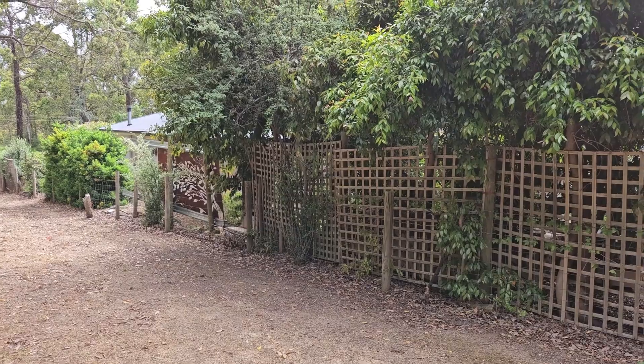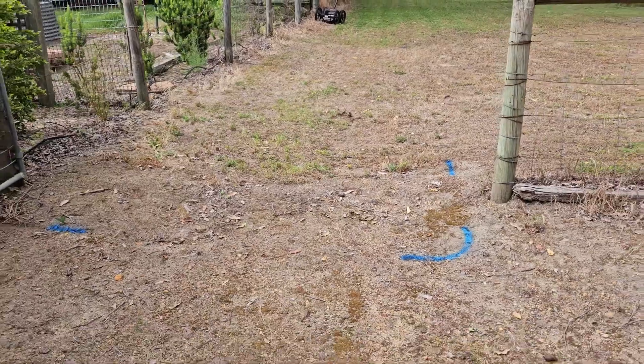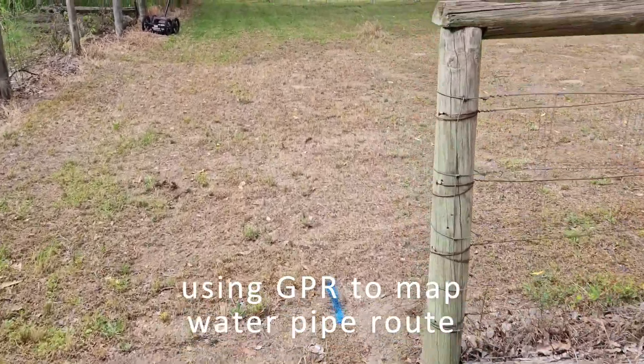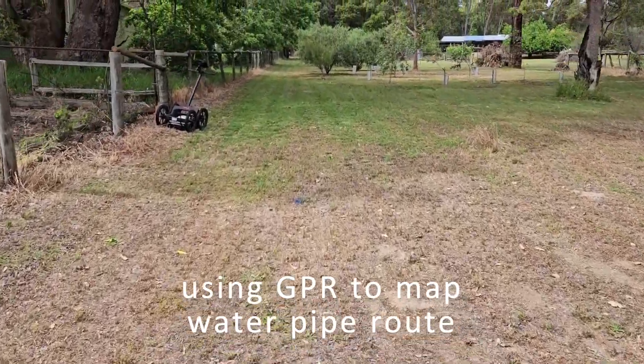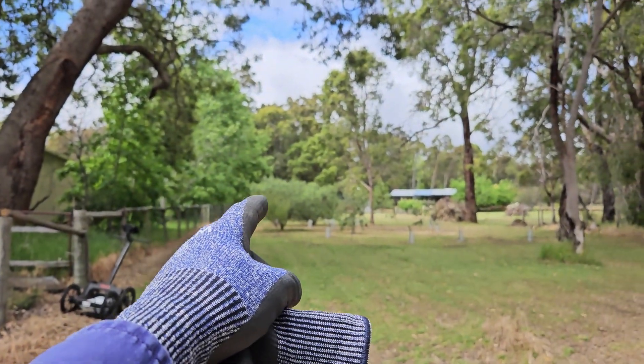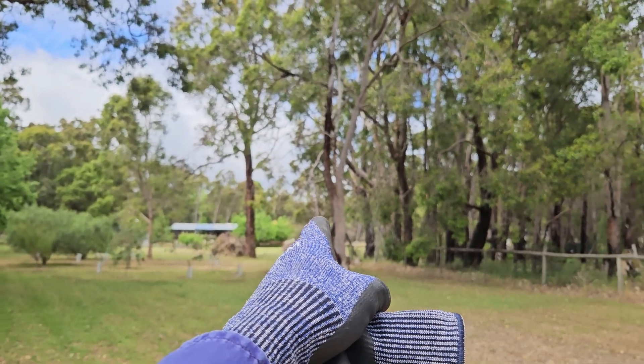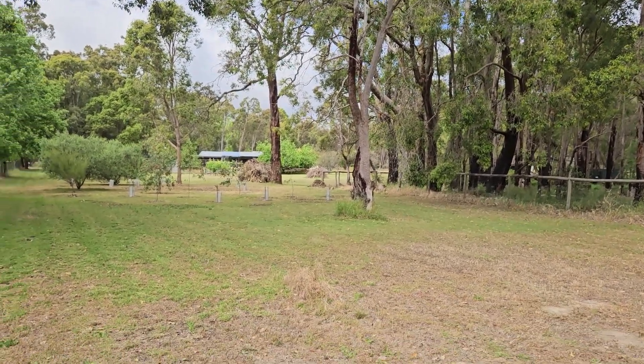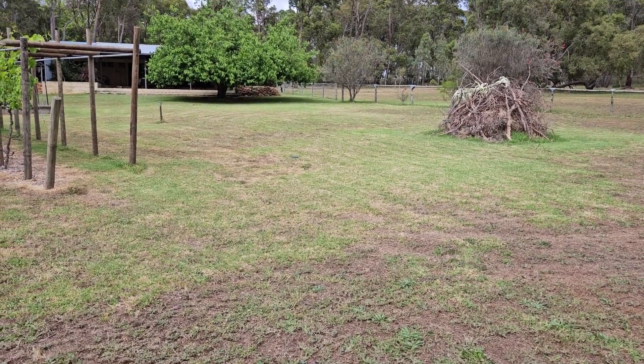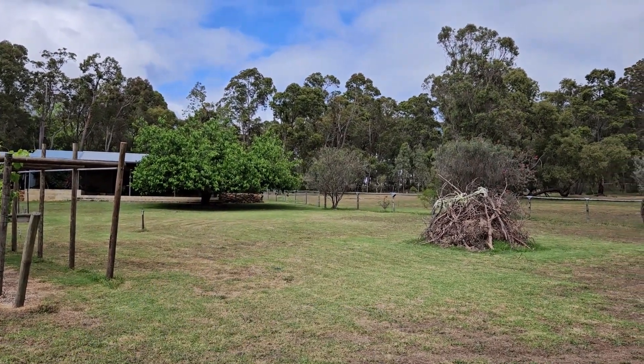I've got the main house behind the bushes there, and with the radar you can see I've already started marking the blue line, which I believe is going to be a poly line. It continues up through around this first set of bushes, then turns right towards this second house, and then up around that house to the water meters on the other side of the property. You can see a straight run of blue dots — that's the pipeline — and behind that is where all the water meters are.